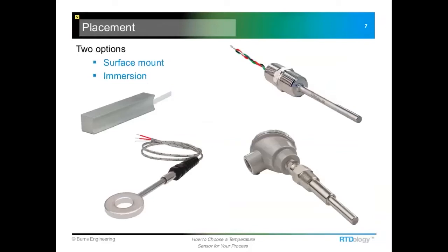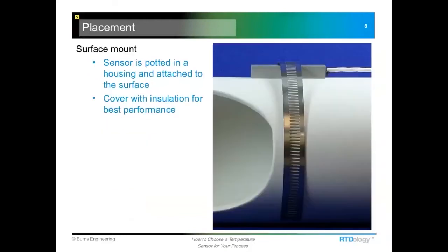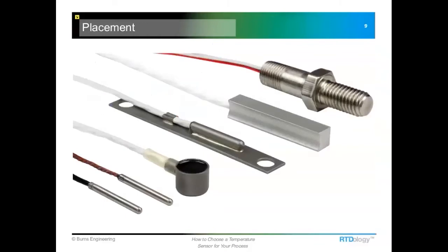First off, we need to select whether we want an immersion style sensor or a surface mount. The surface mount is going to be very easy to install. The immersion sensor requires some sort of a hole in the piping. It's a little more involved to install, but you do get a little better, more accurate measurement in most cases. For the surface mount, there are several different styles. Typically, they just get strapped to the outside of a pipe, and then they require some sort of insulation to cover them up so that you minimize the effects of the ambient conditions on that sensor. For example, if we had a process that was running real hot and you've got just room temperature around it, without insulation the sensor is going to read lower than the actual surface of that pipe. So we do need that insulation to get the best measurement.